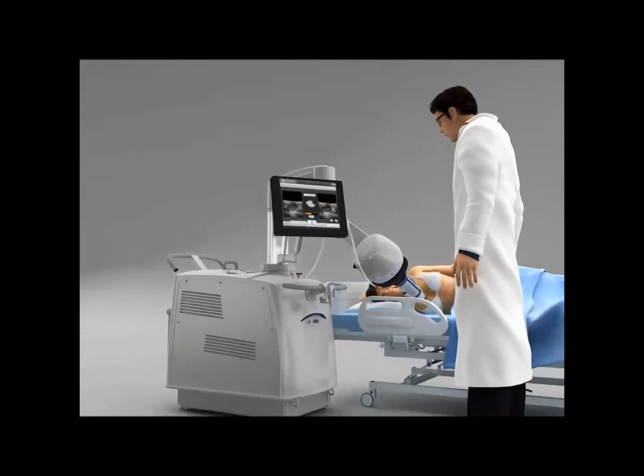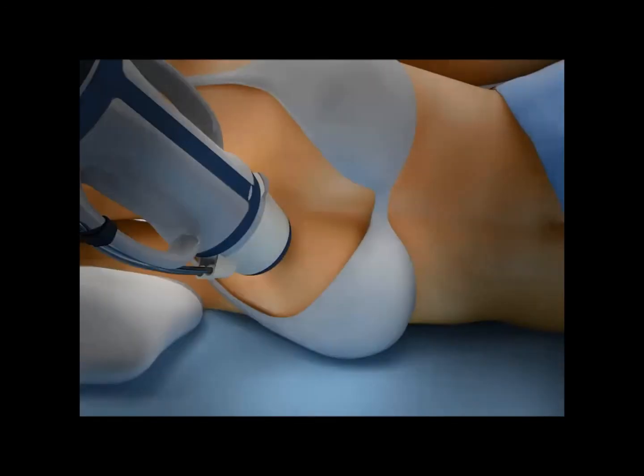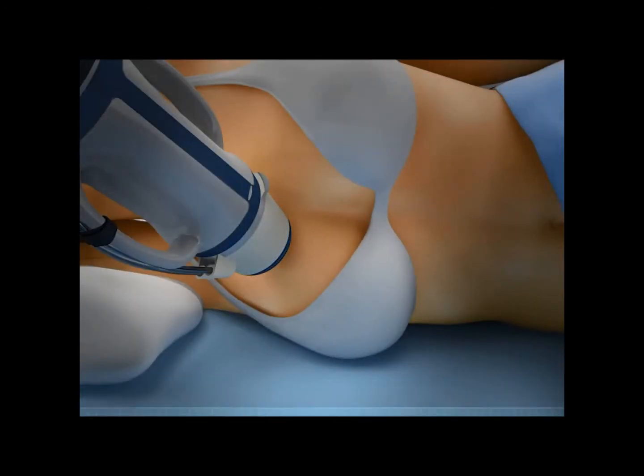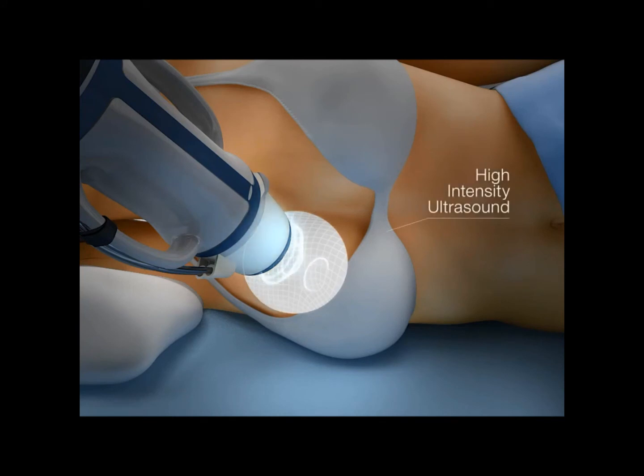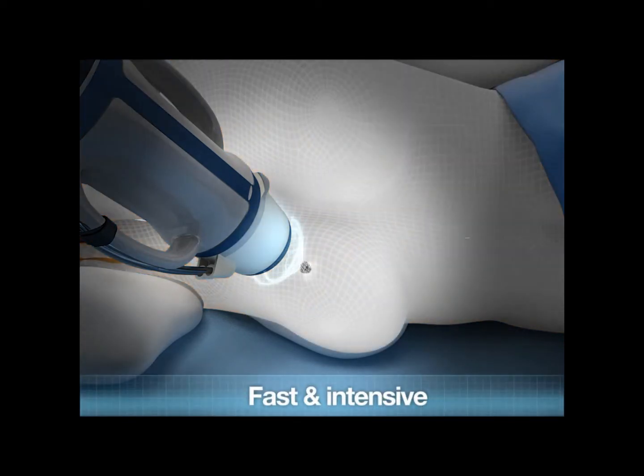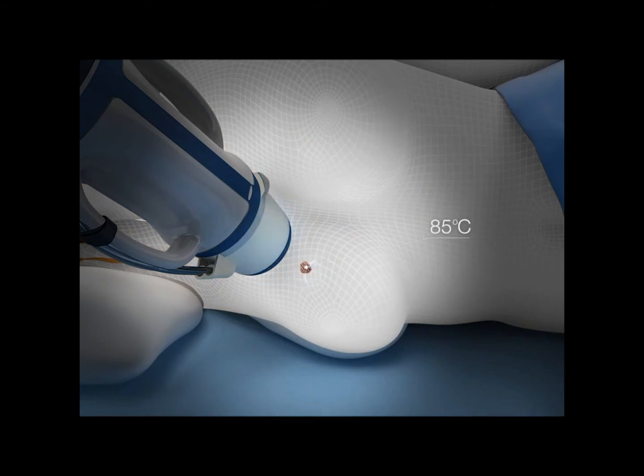The treatment consists of consecutive repeated pulses of HIFU over a pulse-and-pause scheme. HIFU technology focuses high-intensity ultrasound in order to deliver a large amount of sound energy on a confined space, inducing a fast and intensive tissue heating of around 85 degrees centigrade.